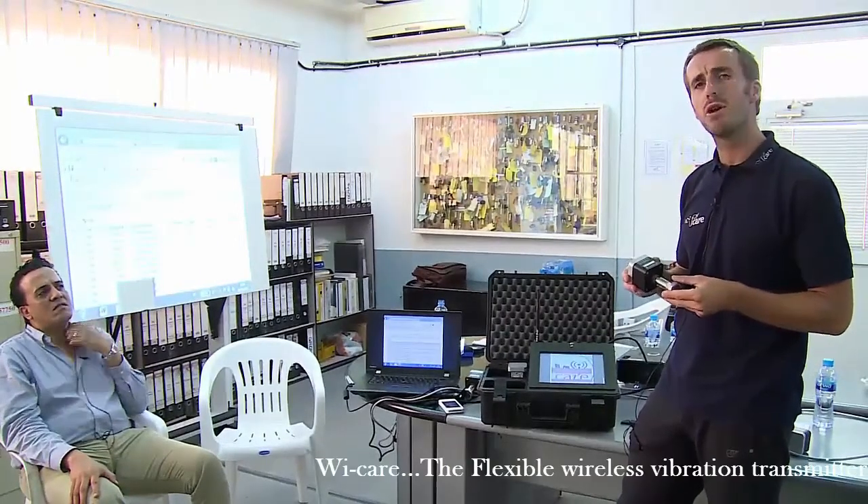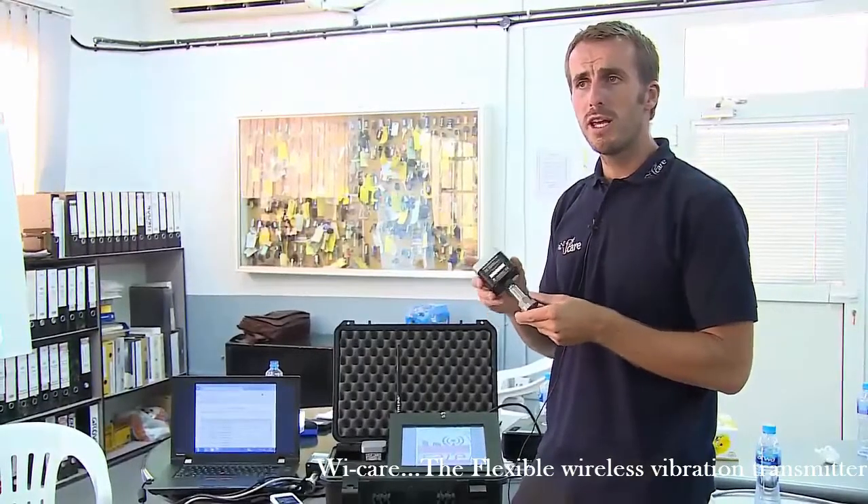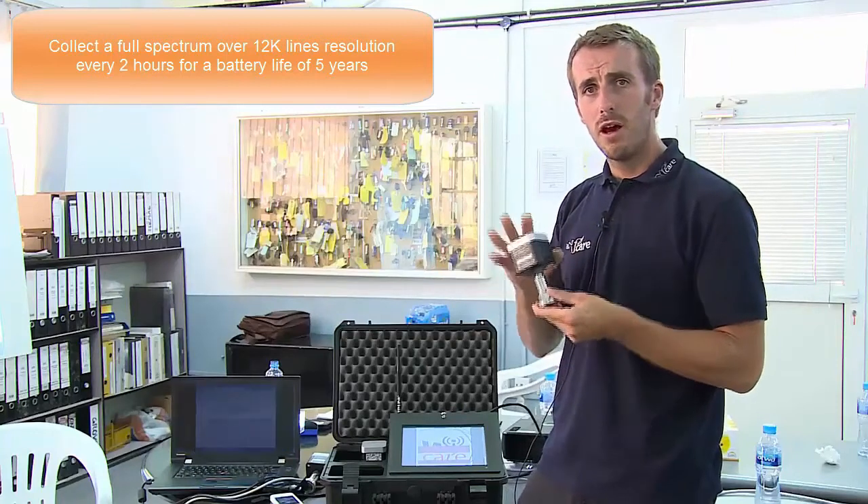How often data is collected is completely manageable by yourself directly on the website. In a basic configuration, the Wi-care arrives at your site collecting a full spectrum every two hours. In this configuration, the battery life of the sensor is designed to last five years. You can reduce that interval to around four or five minutes.